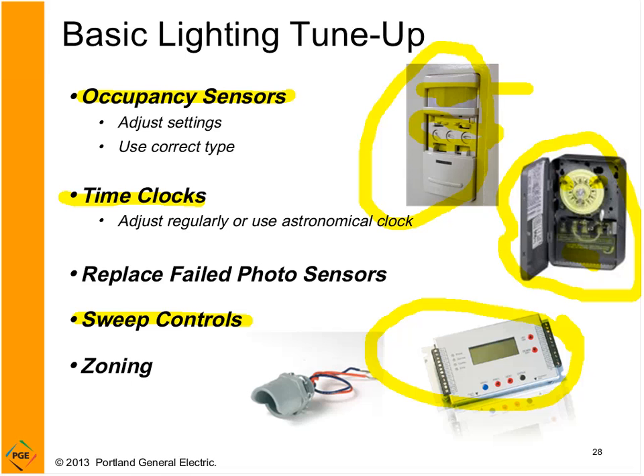You can even give a warning by flashing the lights before they shut off, allowing any occupants still in the facility to turn their own lights back on. If you have sweep controls, another key thing is to program them to sweep off multiple times, to capture anyone who overrides the system.